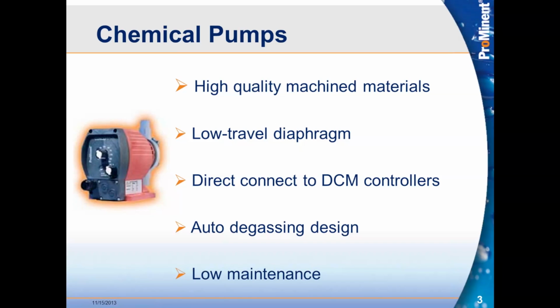Great example of the utilization of this PID in our pumps. And again, we can call this smart disinfection, smart dosing, because we're actually controlling the dosing events to a much, much higher, more precise value, so we can help eliminate overfeeds or underfeeds. A great example of this application is an outdoor facility in Texas I was at late in the summer, and I paced it off, it's probably the longest distance I've ever seen between a pump room and the pool, about 350 yards.